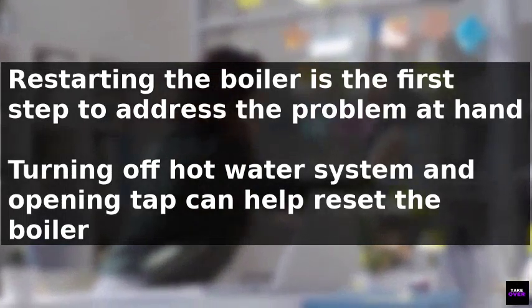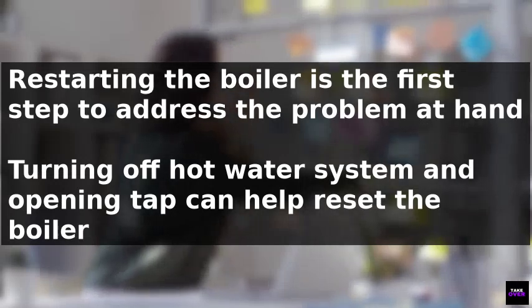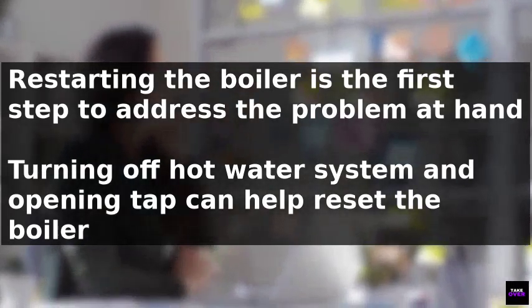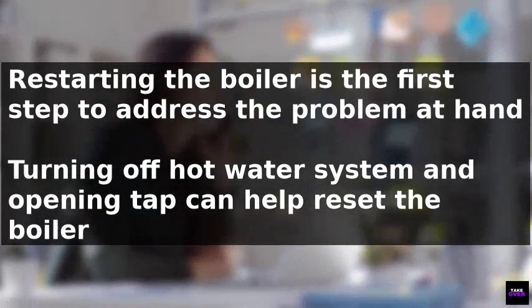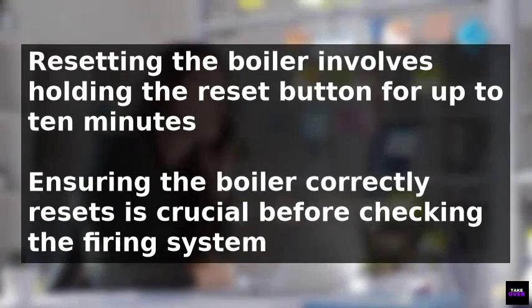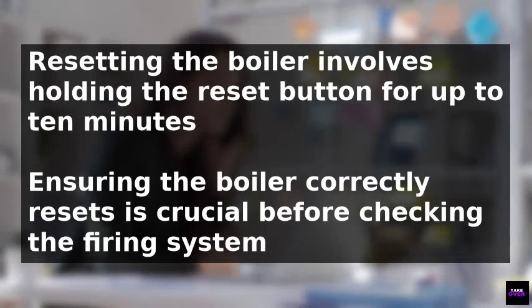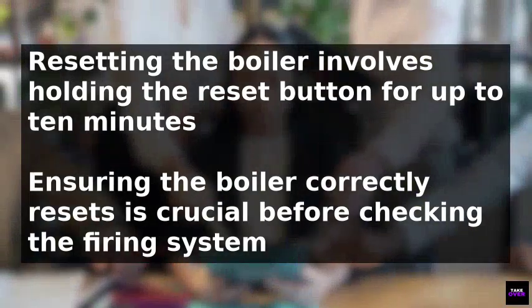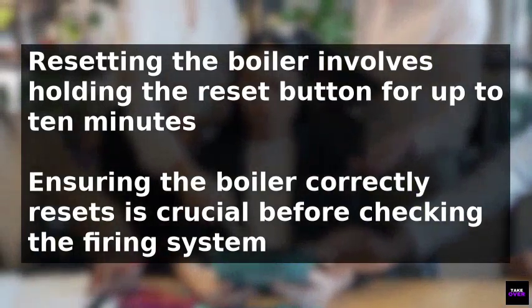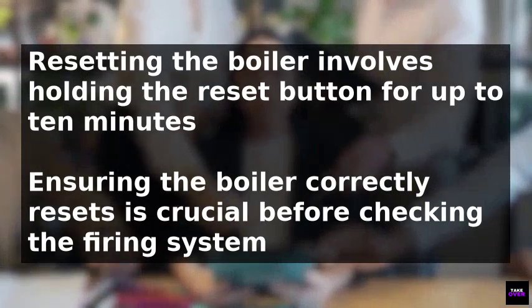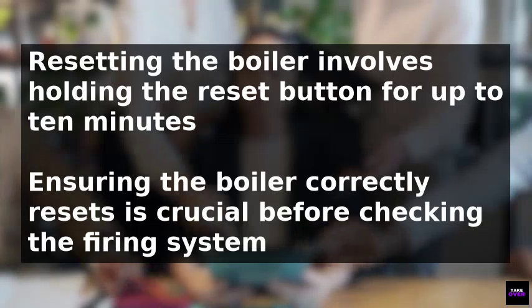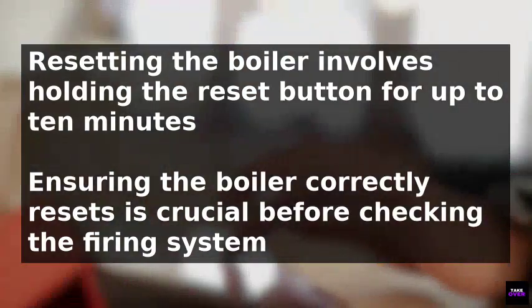This can be done by turning off the hot water system at the main power outlet, then opening the hot water tap to its maximum flow. Next, turn the boiler back on and reset it by holding and pressing the reset button for up to 10 minutes, ensuring the boiler correctly and fully resets before checking the firing system again.